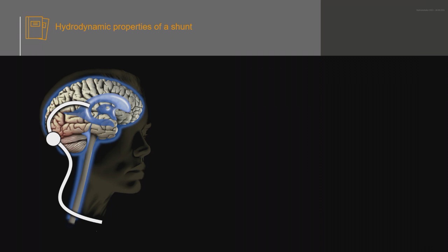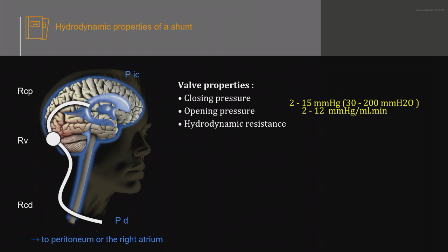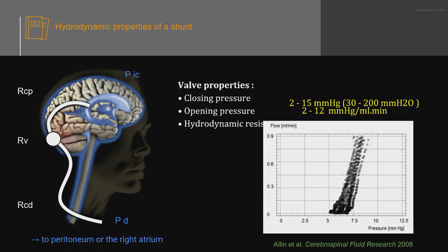So sometimes CSF dynamics is perturbed, and then it needs to have a shunt. So here we have a derivation that is imposed. And it has three components: two catheters and the valve. And the valve has several properties that you can choose. And so these are typical values for the resistance we can choose and the opening and closing pressure. The resistance is nonlinear, and for small flows, the resistance is really nonlinear, but for larger flow, we'll have a constant resistance.